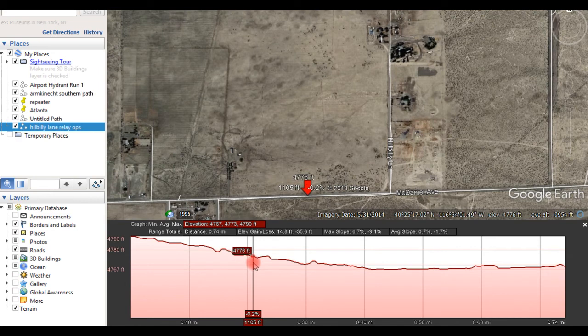So if you did 1,200 feet, so let's say you go right about there, you put an engine, and so then you go to 24. So there's another engine. And then you would need at 36, which would be somewhere out in here, a third engine. So you would have to have 3 engines in a relay to use 2.5 inch hose for this to go to a couple of nozzles if you had a structure up here.